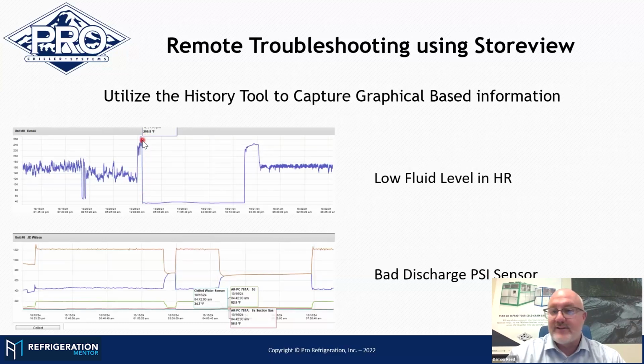And then of course we get a compressor safety trip. So now our discharge temperature comes down, it just sits idle. And then here's where we got it reset. We watched it operate. We're like, man, that's still running really high. So between this point and this point, we identified, oh, we've got to get some fluid over into the heat recovery system, get it in, and everything's running. It was still running a little high. I think things tapered off once it got into its operation. But from here to here, this was the amount of time it took us to troubleshoot it.